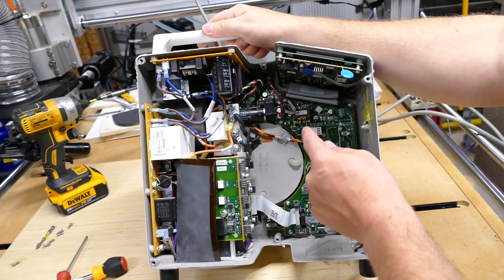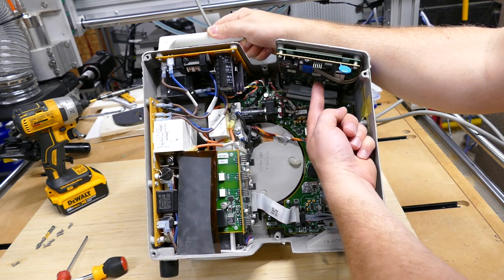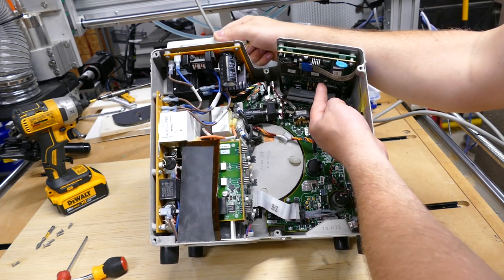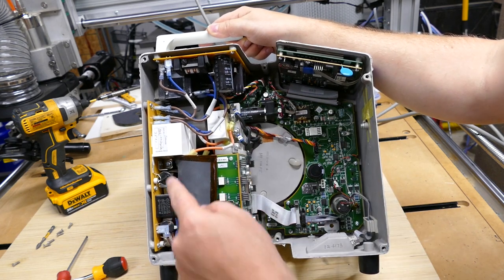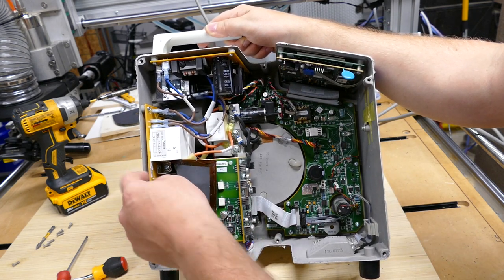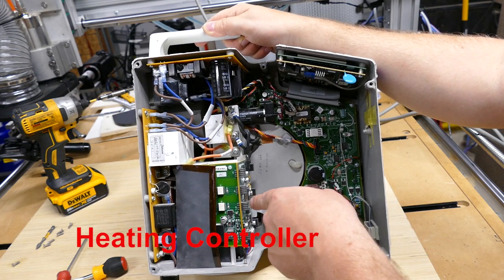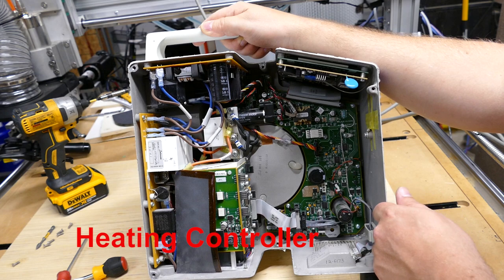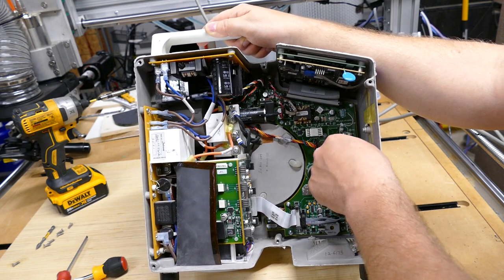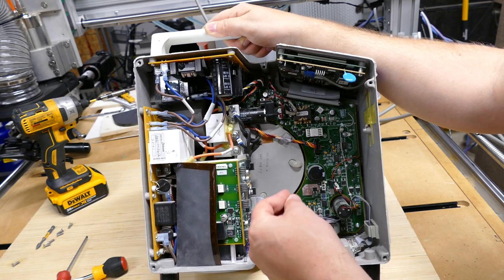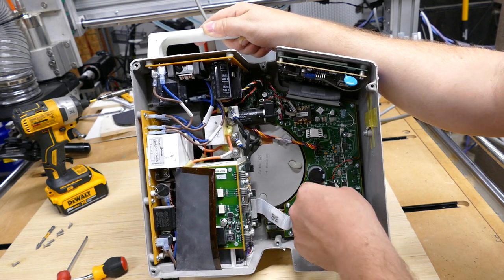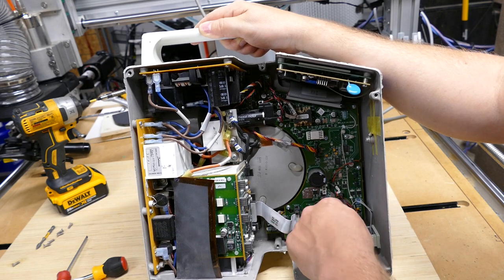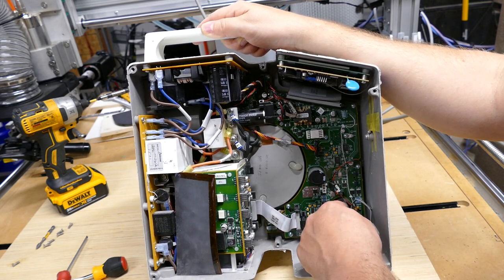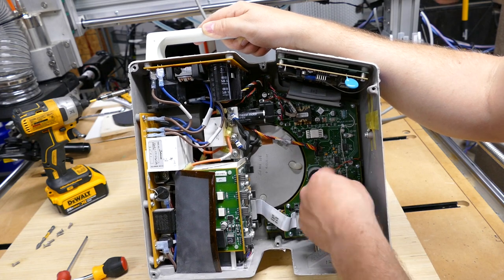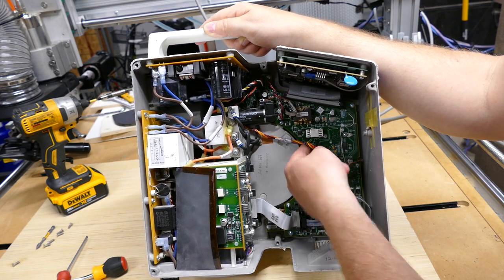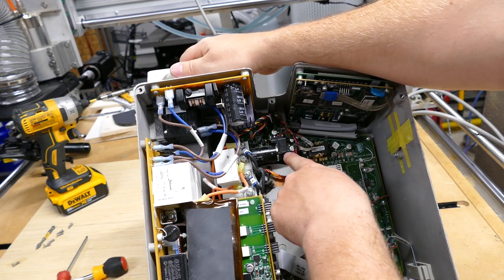Inside this beast, you'll see you have your main board down here. You'll have a display control board up here, which also has your CPUs on it. You have a power supply here, a power distribution and relay board on the back. And over here, these are the motor drivers for the peristaltic motor. Underneath this board, there's going to be several points where sensors will plug in. So you have to be very careful if you ever have to remove this board. Right here, you can see a gear reduction drive on this motor. This is your pinch valve. And it just plugs in right there locally. You got some other sensors that plug in locally. Up here, I hope the camera can pick it up.